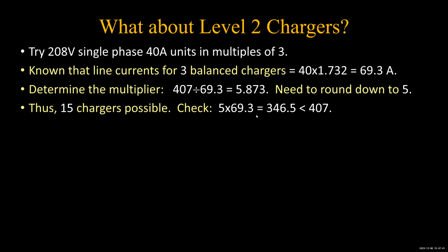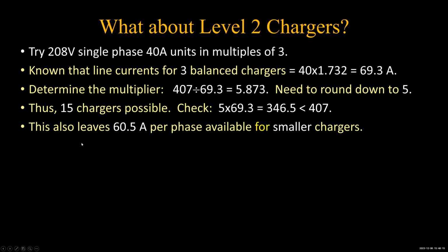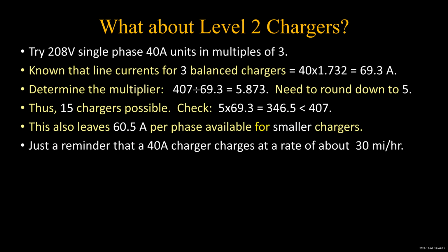5 times 69.3 is 346.5. It's less than 407. We expected it would be, but we can't go more than 5 or we'll be higher, because we're going to have that 1.732 factor in. So that's less than 407, but we can use that remainder for lower power chargers or whatever else. But let's see what we can get with just 15 chargers. What's the possibility here?